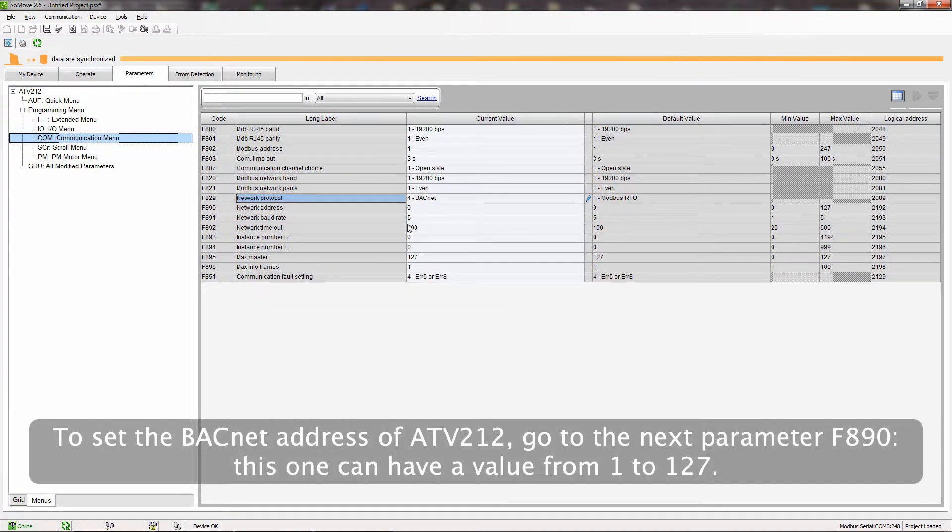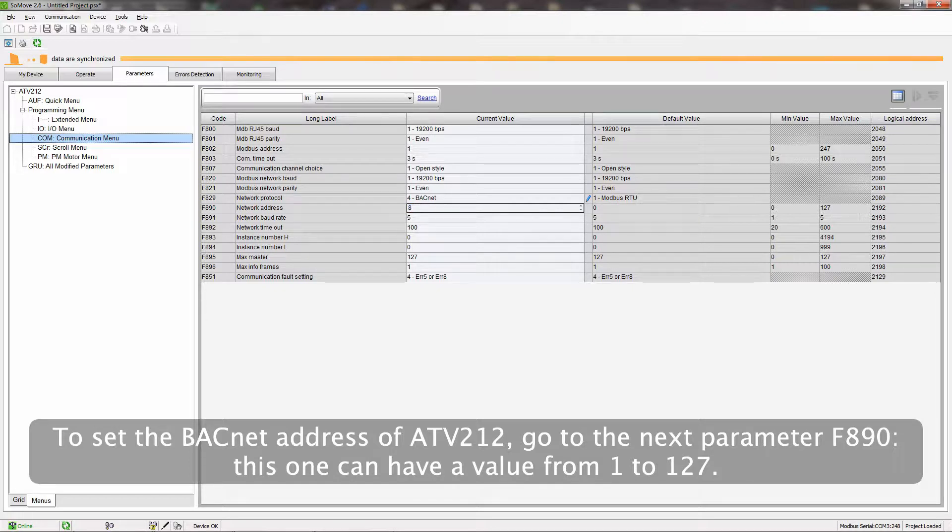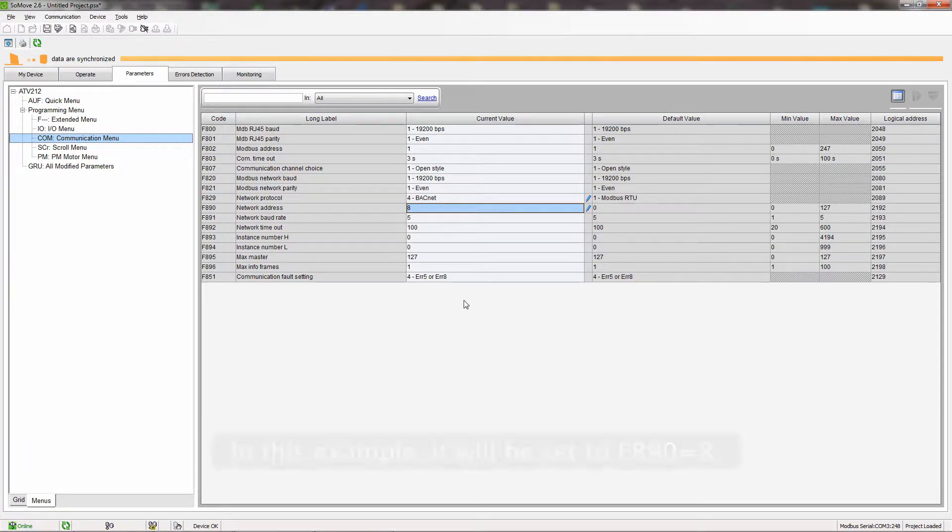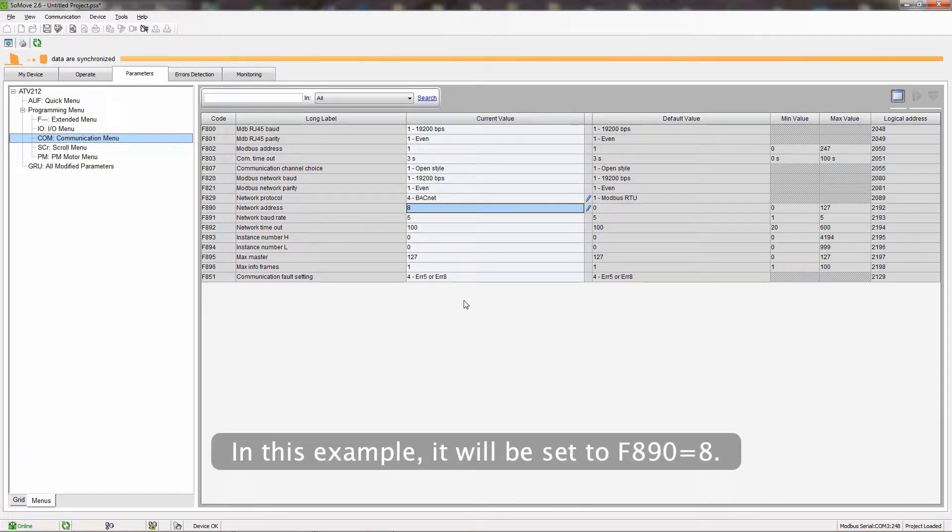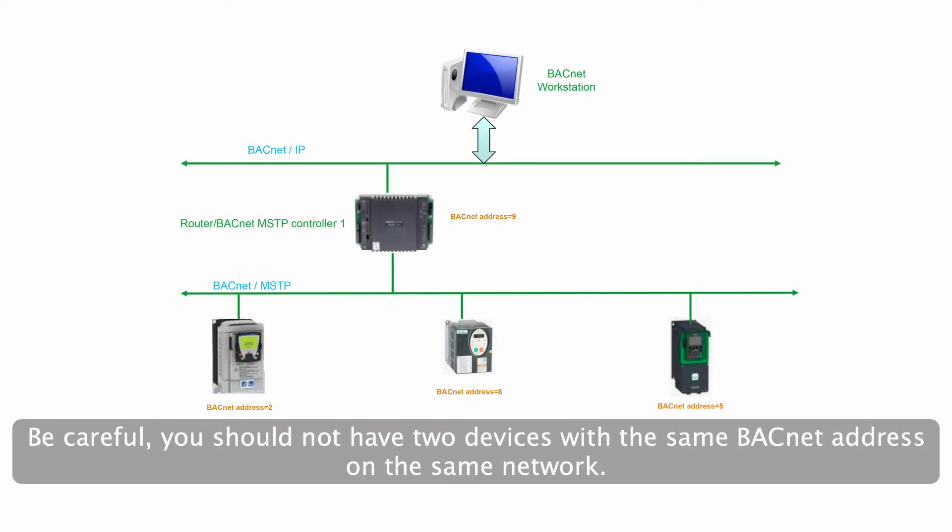To set the BACnet address of ATV212, go to the next parameter F890. This one can have a value from 1 to 127. In this example, it will be set to F890 equals 8. Be careful, you should not have two devices with the same BACnet address on the same network.